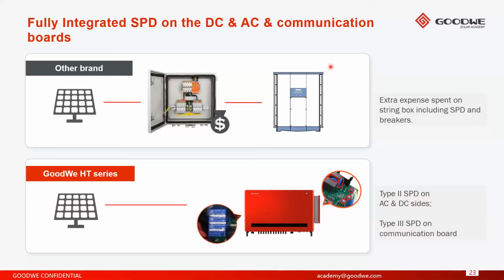So less investment, as I mentioned, in traditional commercial systems, the need of a combiner box with perhaps integrated SPDs, type 1 or type 2, was a requirement, but with the introduction of string inverters, which are now for large-scale PV plants, we include the surge protection devices, as you can see, inside the inverter itself, both on the AC and DC side, and we have a type 3 SPD on the communication board. As I mentioned before, you can also have the option of having a type 1 surge protection. However, it must be ordered directly from the factory.